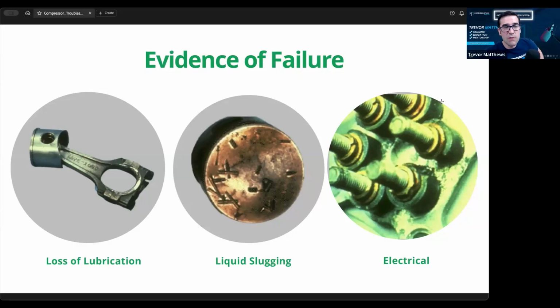Let's talk about that. What are the things that you would see if you don't have a properly evacuated system in a compressor? Well, first of all, when you're evacuating a compressor, you're just trying to get the non-condensables out of it. You're really not trying to pull moisture out of it, unless you find that you have a system with a leak in it that might have moisture in there. And if that's true, you better have a brand new vacuum pump and some very large hoses to pull the actual moisture out. But just remember, when you're pulling a vacuum, you're just trying to pull the non-condensables out of the system.